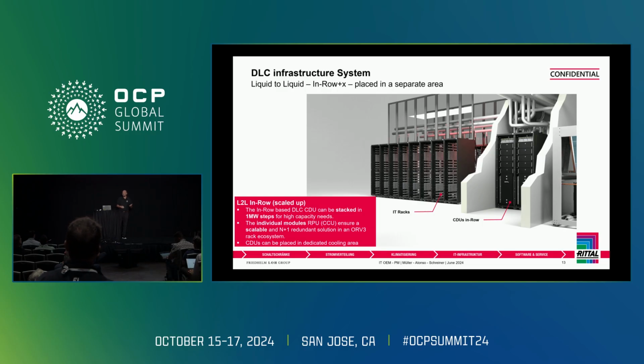Another example, maybe you want to save your white space a little bit more. So you're running precious space within your white space if you're running any of the high power products. So you want to put it out into the gray space somewhere outside the fan walls maybe. This is an example of scaling it from 1 megawatt to 2 megawatts. So outside of that space right now, there are 2 of those 1 megawatt units operated, plumbed into the white space, operating some very high power products if it's needed to go to that level of scalability.